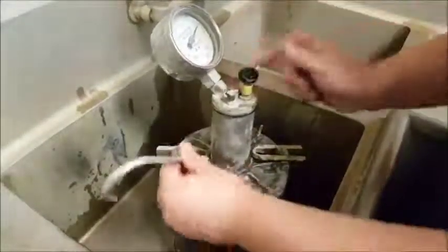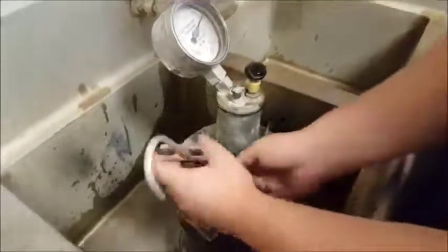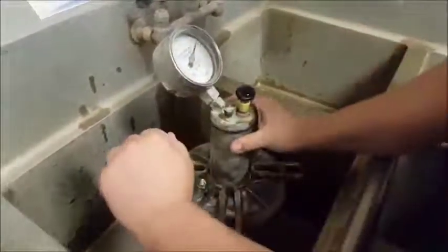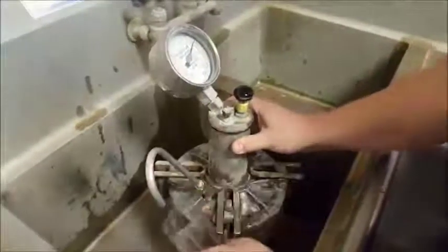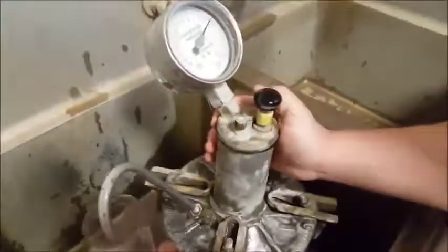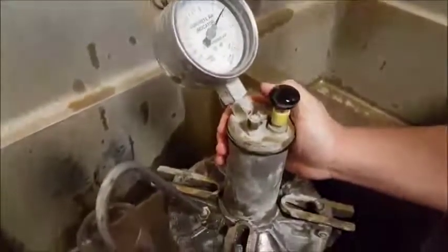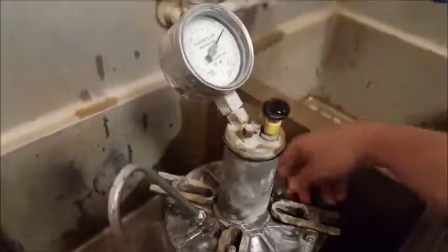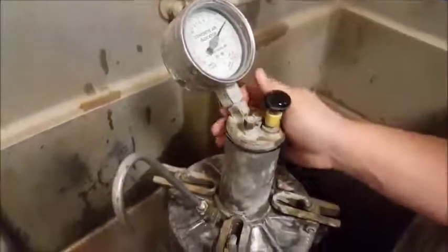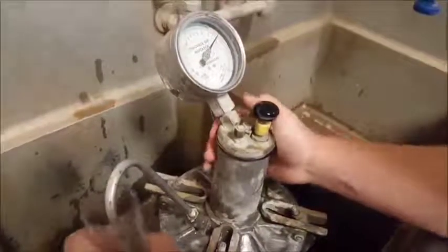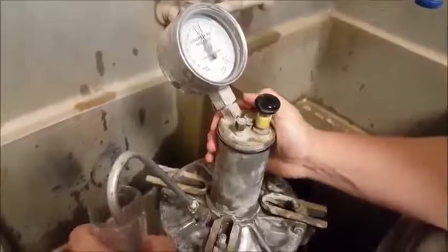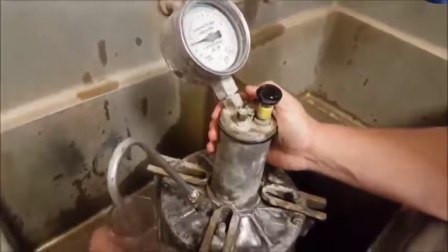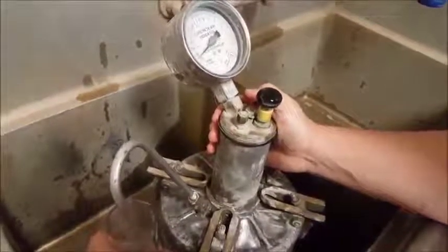Then we're going to screw the curved tube into the same side that had the straight tube underneath. And then we're going to fill our calibrated tube here slowly and carefully so as not to overfill it. Oops, make sure this petcock over here is closed first, that your tube's empty. We're going to fill this up. Careful not to overfill it.